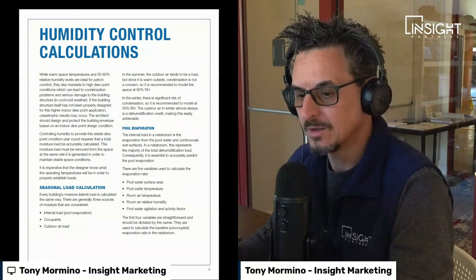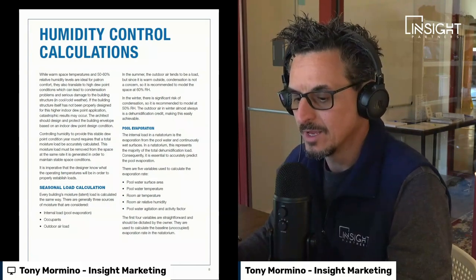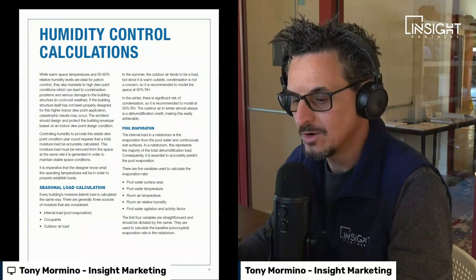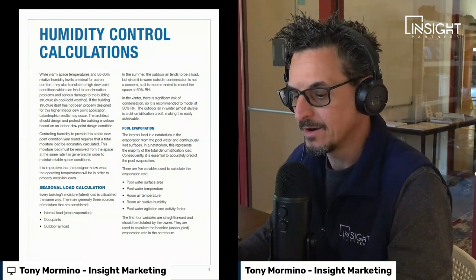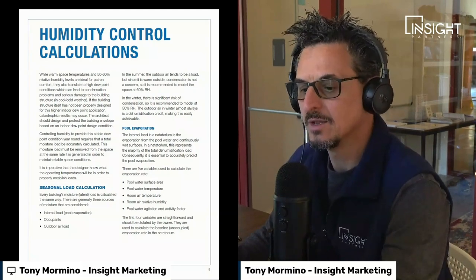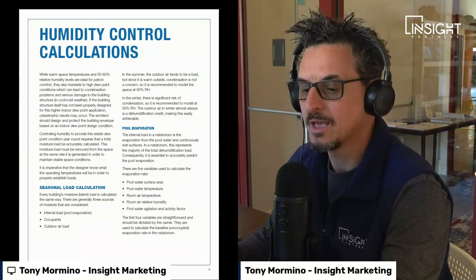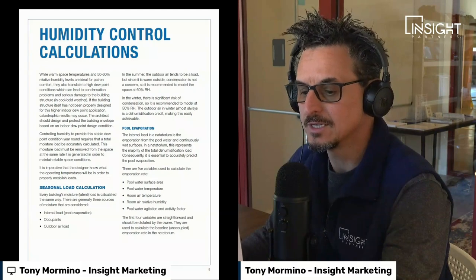Moving on to pool evaporation. The internal load of a natatorium is the evaporation from the pool water and continuously wet surfaces — this represents the majority of the total dehumidification load, so it is essential to accurately predict pool evaporation. There are five variables used to calculate the pool evaporation rate: one, pool water surface area; two, pool water temperature; three, room air temperature; four, room air relative humidity; and five, pool water agitation and activity factor. The first four variables are straightforward and should be dictated by the owner.